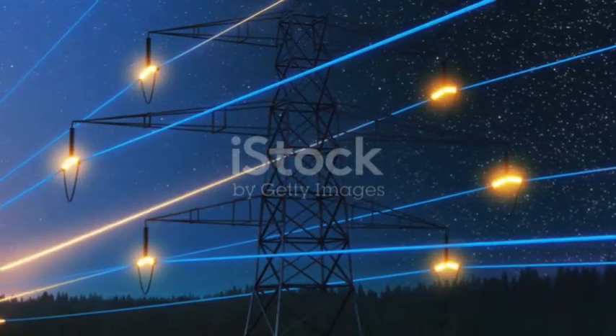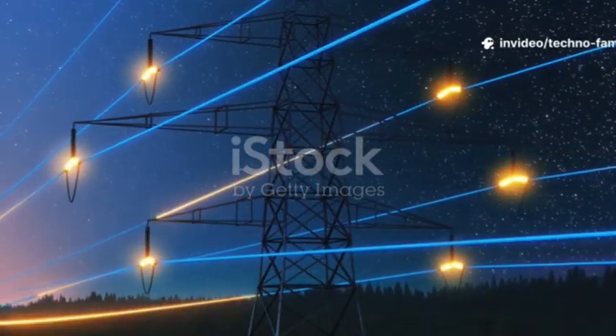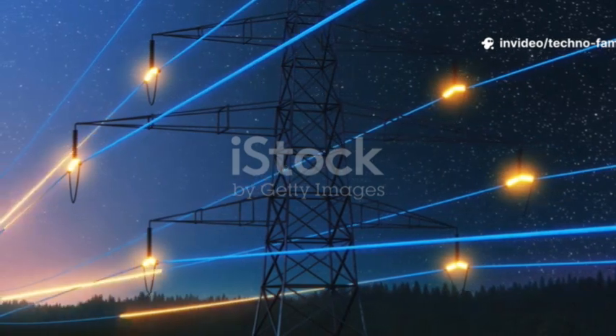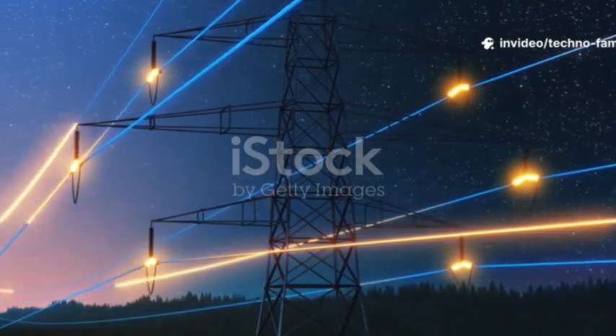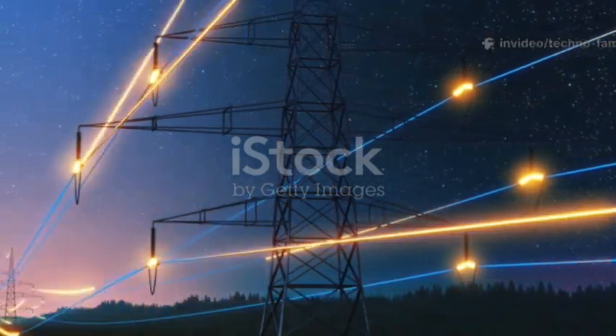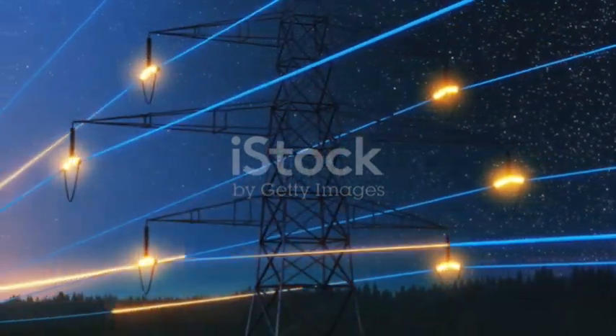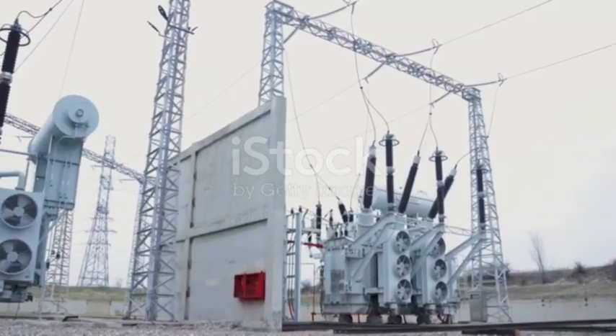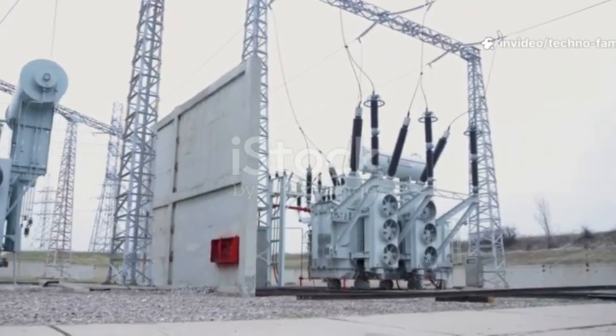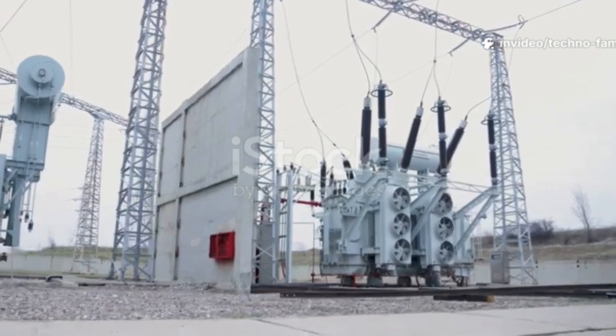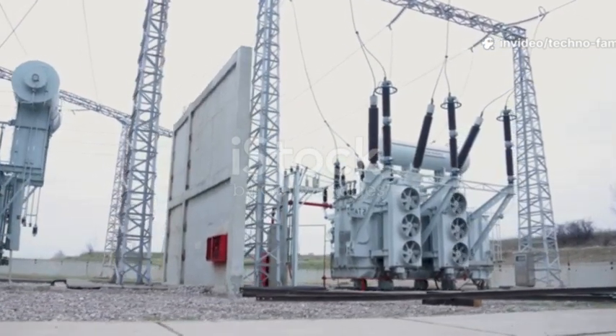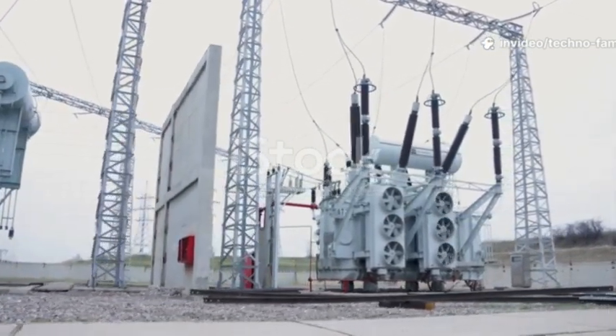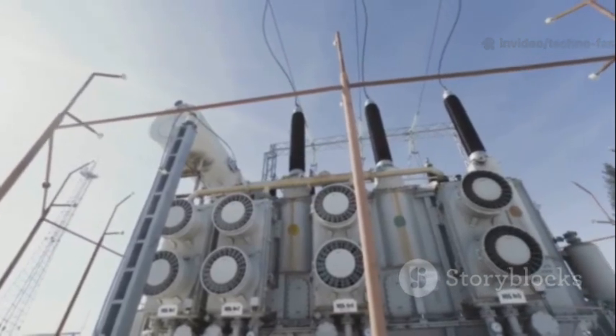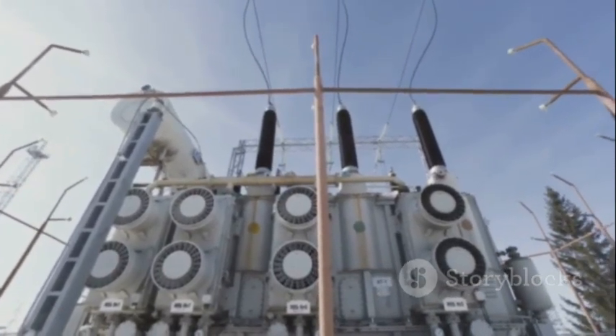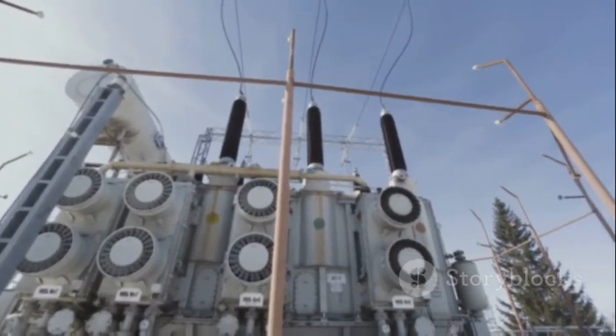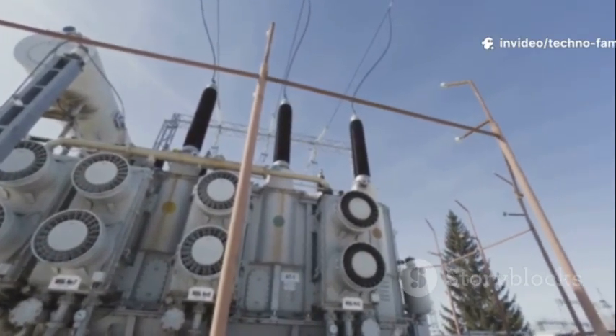The problem: power losses are proportional to current squared, I²R losses. If you try to push large power over long wires at low voltage, current is huge. Big losses and big wires needed. The solution: increase voltage. Transmit at high voltage so current is lower for the same power. Use step-up and step-down transformers to manage at both ends. Over time, this led to development of high-voltage AC systems, then HVDC, improved insulation materials, standards, safety procedures.